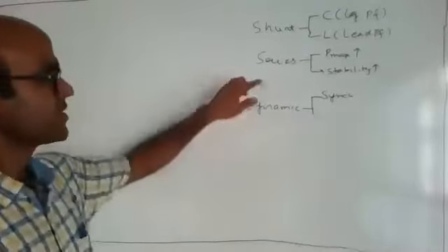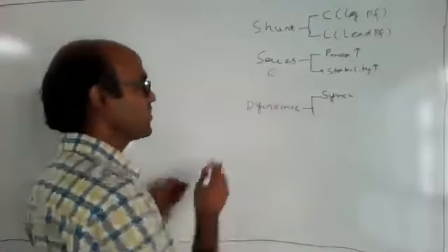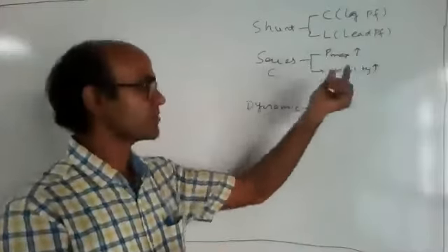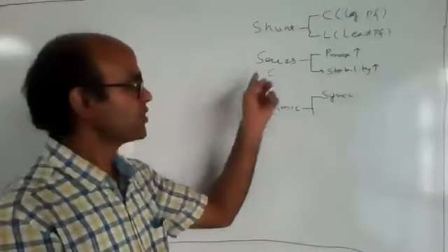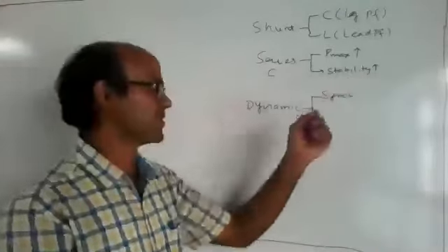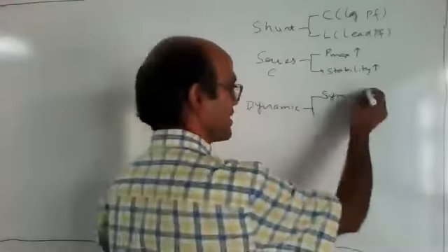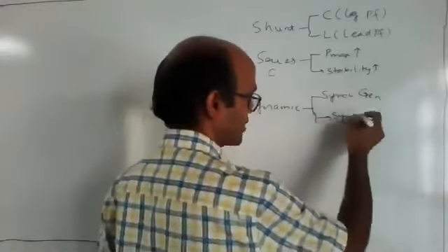And then series capacitor. When will we use a series capacitor? If we want to increase the power transfer capability and to improve the stability. By using a series compensator, we can also improve the stability margin. Then we have seen dynamic compensators, that is synchronous generator and synchronous motor.